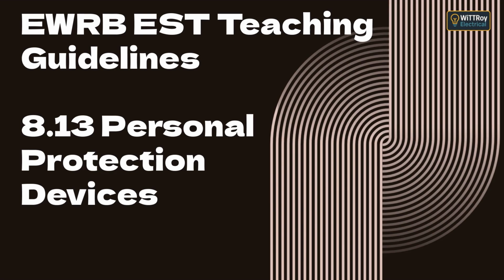Now for Topic G, RCDs used with handheld appliances. Handheld tools like drills, grinders, and extension leads are high risk because the user's body completes the path to Earth. Portable RCDs, PRCDs, are used for this reason. When plugged between the supply and the tool, the RCD trips instantly if any current leaks through the user. For example, a PRCD plugged into a portable lead on a building site must trip within 300 milliseconds at 30 mA, or faster if 10 mA rated.